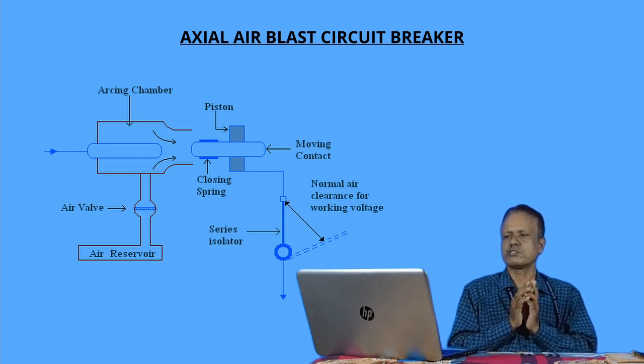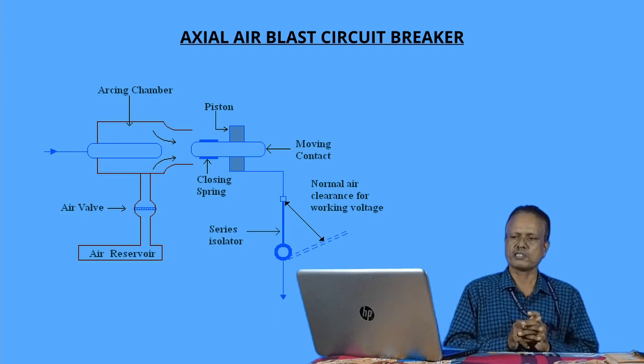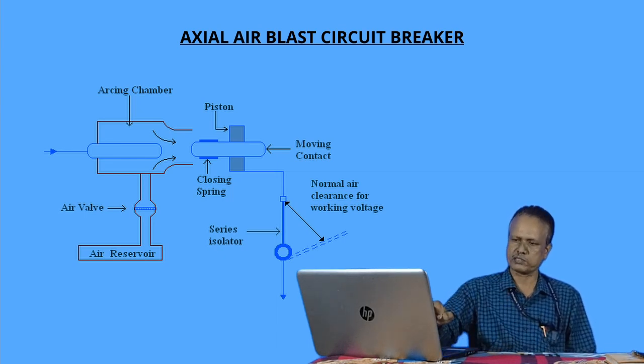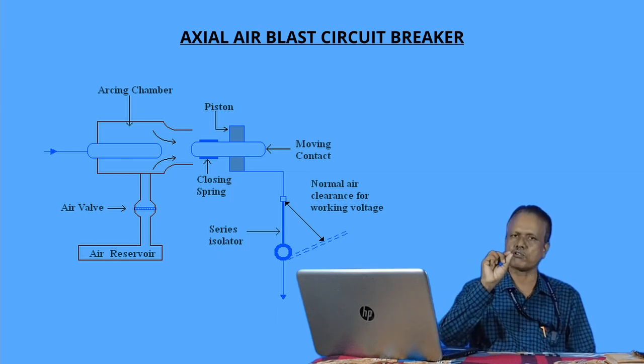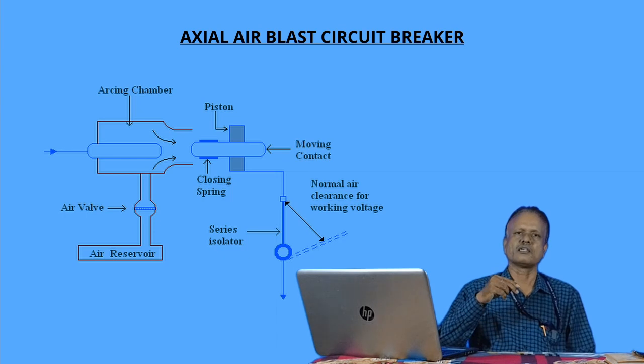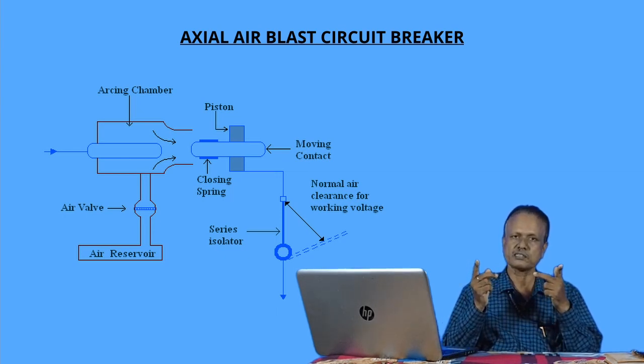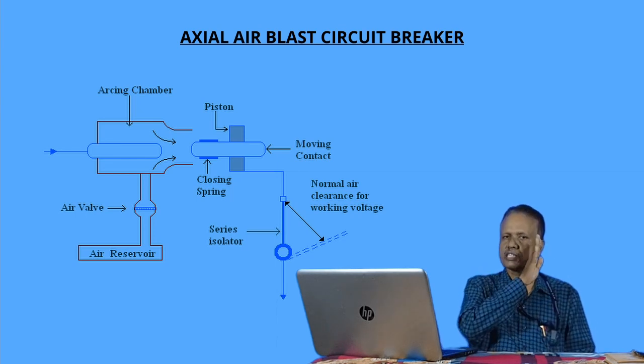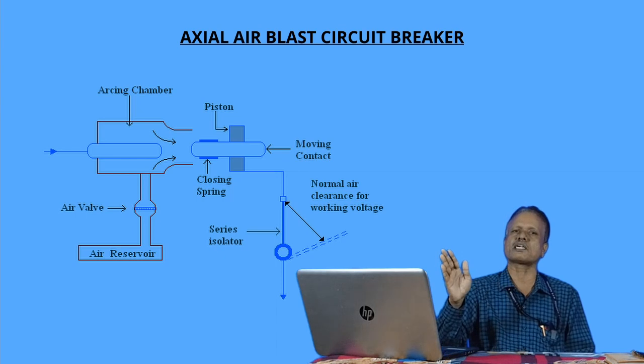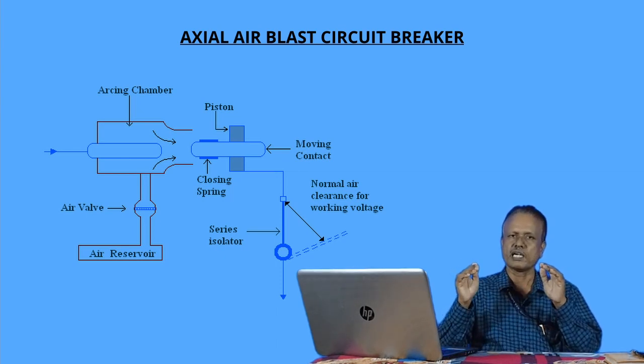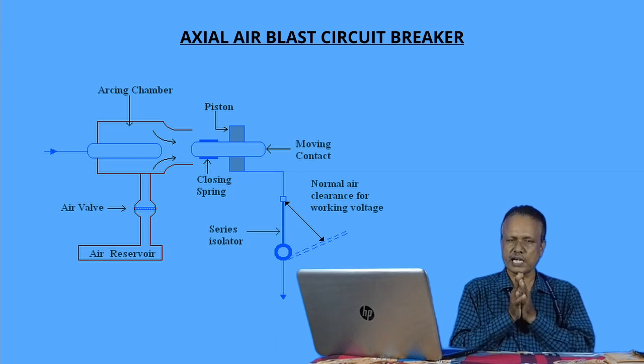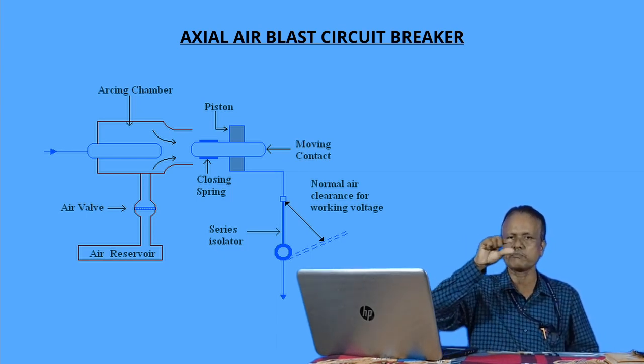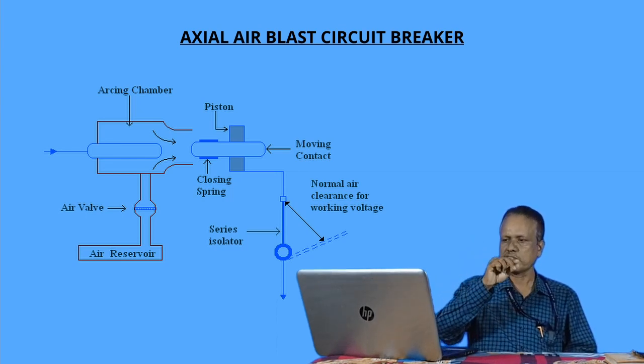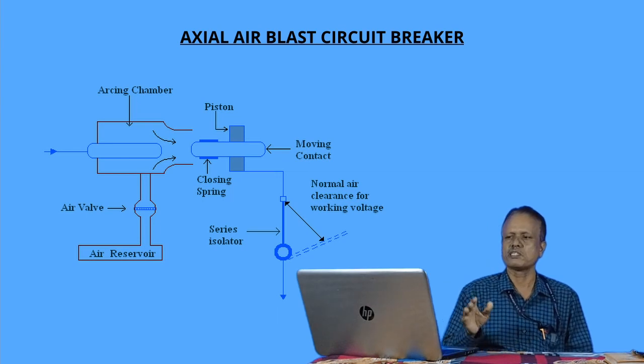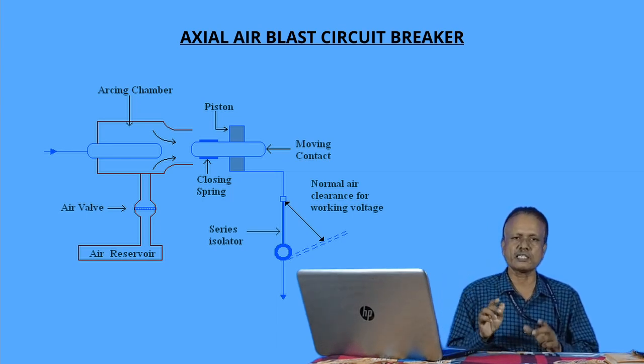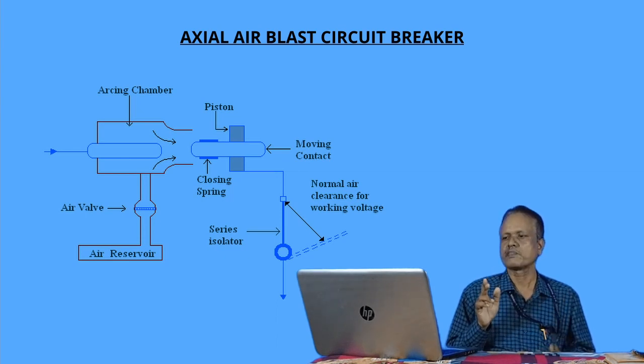So if we come to its operation, when a fault occurs, at that time a tripping impulse causes the air valve to open and thereafter the air is forcefully blasted into this arcing zone, so that it moves the moving contact away from the fixed contact, thereby an arc is developed. Since this constant flow of air is blasted into this arcing zone, gradually the diameter of the arc reduces and finally the ionized particles are swept away from between these two contacts, and as a result the dielectric strength increases and the arc is extinguished.